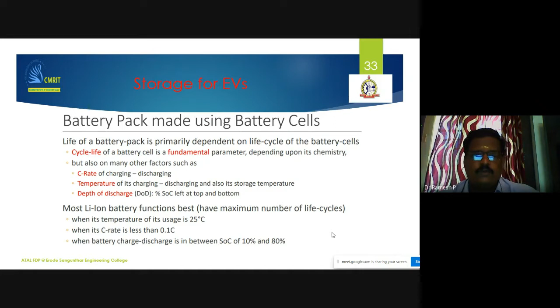The C rating we can follow is 0.1 C. The battery SOC we have to maintain is between 10% and 80%. That means you should not bring the SOC to 0%. That is the meaning. So DOD is a percentage of SOC. We have to keep a margin left at the top and bottom in charging and discharging. We have to maintain a minimum of 10%. For example, for a 48-volt battery, SOC 0% is 43 volts. So we have to maintain more than that and should not go further below it.